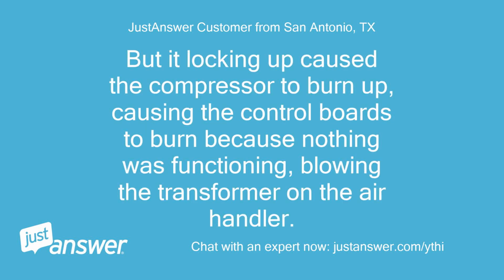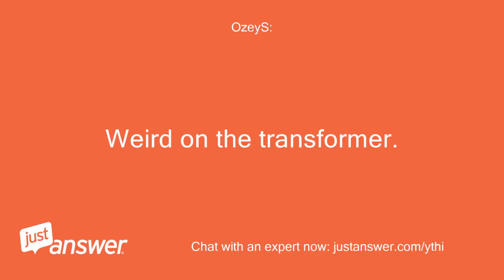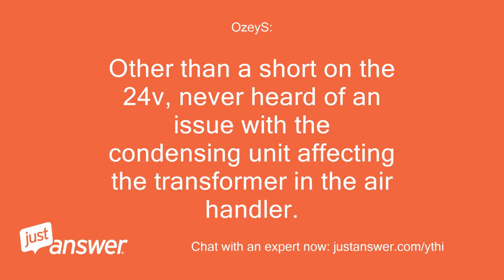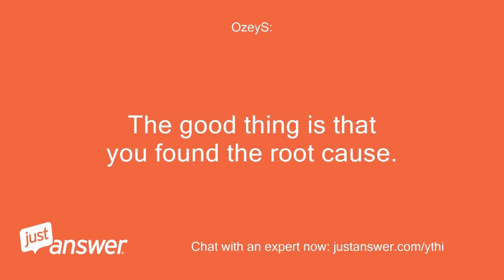But it locking up caused the compressor to burn up, causing the control boards to burn because nothing was functioning, blowing the transformer on the air handler. Weird on the transformer. Other than a short on the 24V, never heard of an issue with the condensing unit affecting the transformer in the air handler. The good thing is that you found the root cause.